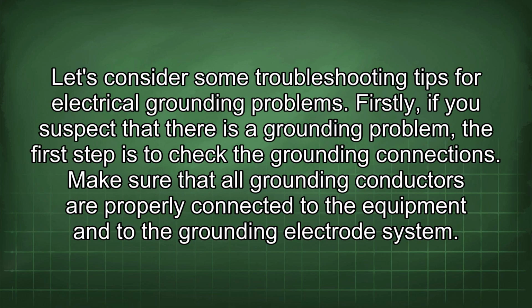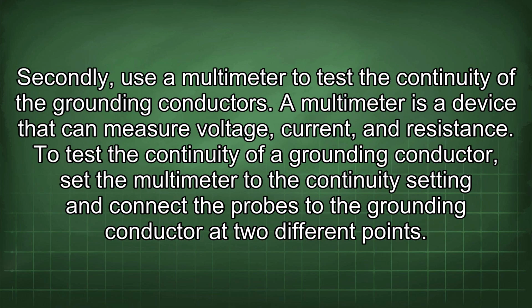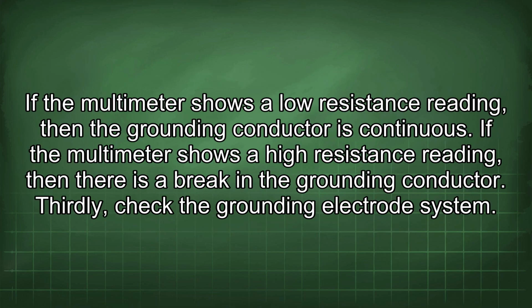Let's consider some troubleshooting tips for electrical grounding problems. Firstly, if you suspect that there is a grounding problem, the first step is to check the grounding connections. Make sure that all grounding conductors are properly connected to the equipment and to the grounding electrode system. Secondly, use a multimeter to test the continuity of the grounding conductors. A multimeter is a device that can measure voltage, current, and resistance. To test the continuity of a grounding conductor, set the multimeter to the continuity setting and connect the probes to the grounding conductor at 2 different points. If the multimeter shows a low resistance reading, then the grounding conductor is continuous. If the multimeter shows a high resistance reading, then there is a break in the grounding conductor.